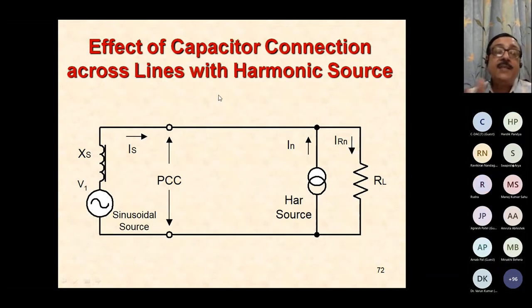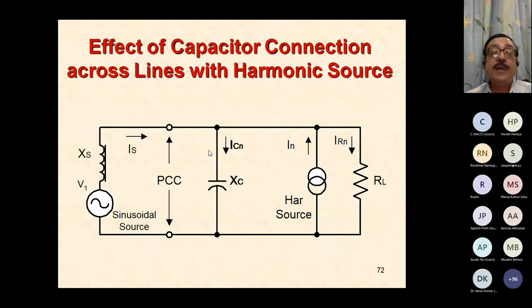Now let's come back and see what happens if I try to put a capacitor across the lines in the presence of a harmonic source like what I have shown here. So this is my earlier system model, where I have the sinusoidal supply and its own supply reactance. This is my PCC. This is the harmonic source, my converter, which is injecting harmonics into the line, and I have just added a resistive load. And I decide to improve upon the power factor by putting a capacitor.